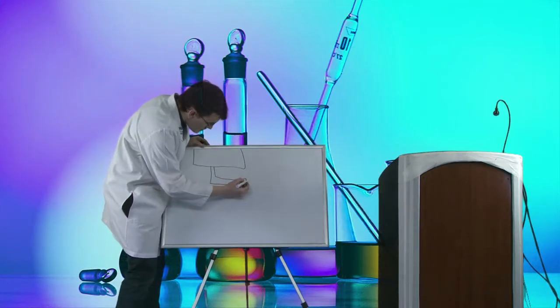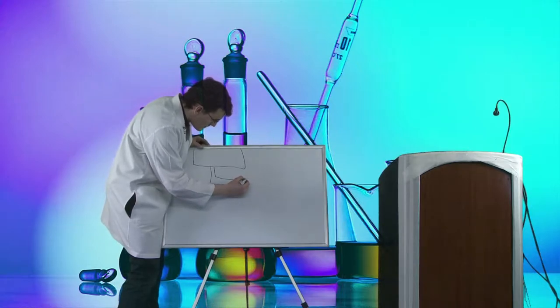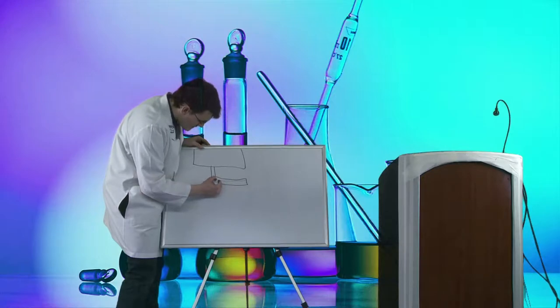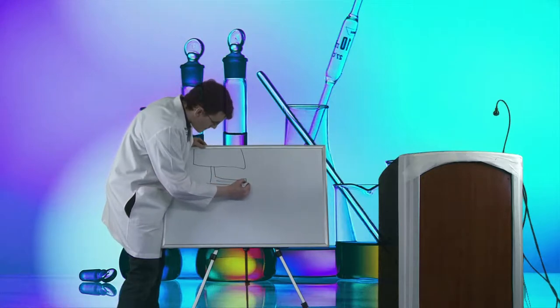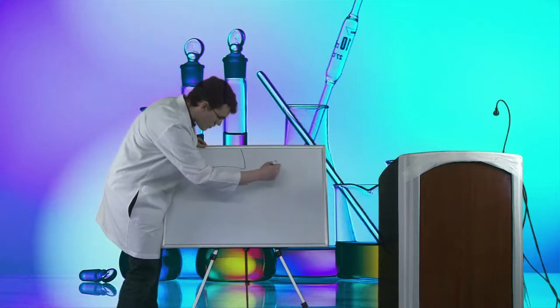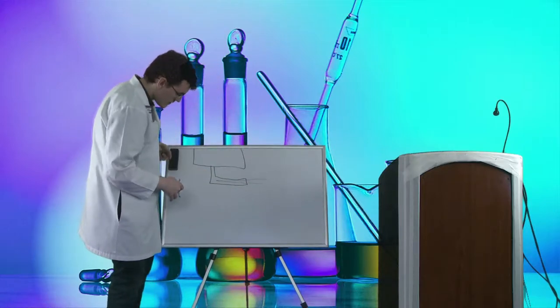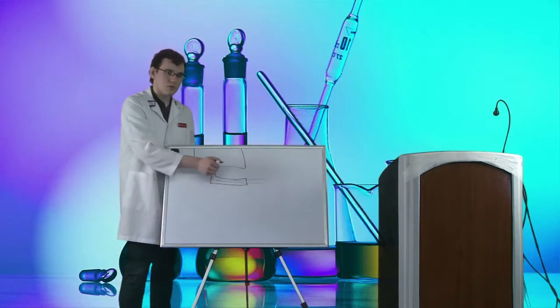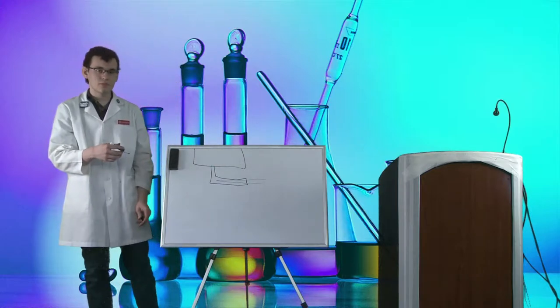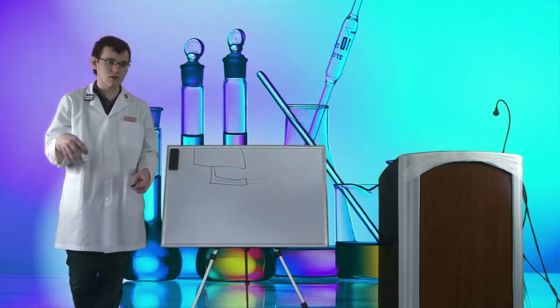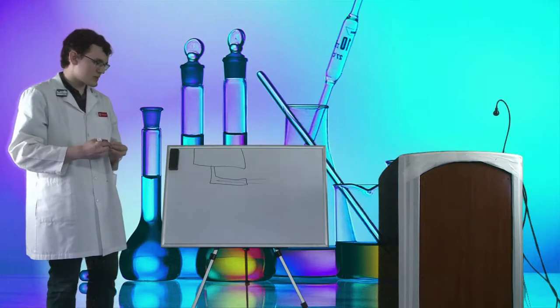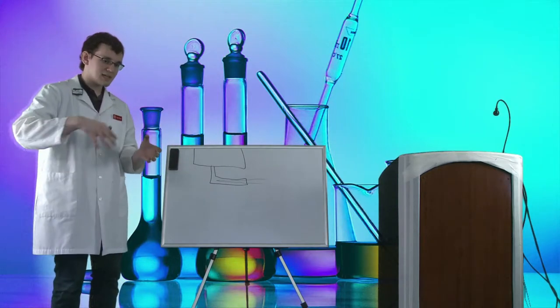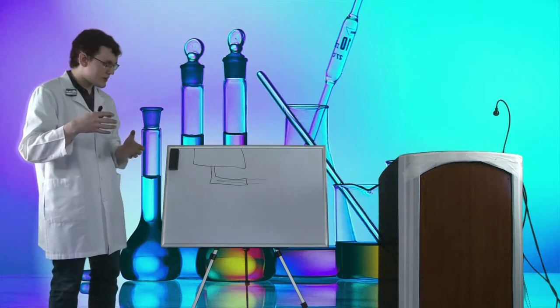Whereas the thermocouple gauge uses a separate temperature sensor, the Pirani gauge uses the metal wire itself as its own temperature sensor. We alternate between running current to heat the wire and measuring its resistance to see how hot it is — keep it hot and measure it, repeatedly. This gauge can measure from roughly atmospheric pressure — though it's more accurate from about 400 Torr — down to the negative 5 or negative 6 range. It's more sensitive than a thermocouple gauge but more expensive, and it's the type of gauge the SEM uses most of the time.